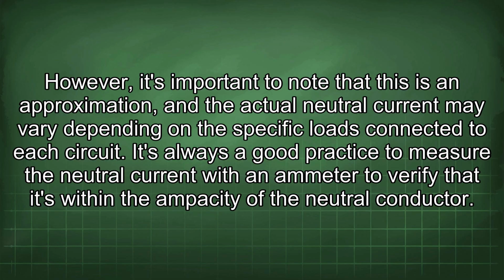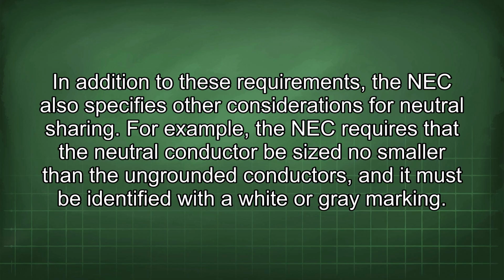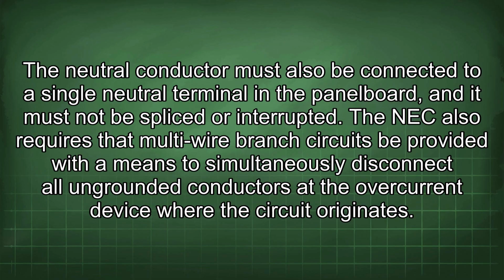However, it's important to note that this is an approximation, and the actual neutral current may vary depending on the specific loads connected to each circuit. It's always a good practice to measure the neutral current with an ammeter to verify that it's within the ampacity of the neutral conductor. In addition to these requirements, the NEC also specifies other considerations for neutral sharing. For example, the NEC requires that the neutral conductor be sized no smaller than the ungrounded conductors, and it must be identified with a white or grey marking. The neutral conductor must also be connected to a single neutral terminal in the panel board, and it must not be spliced or interrupted.